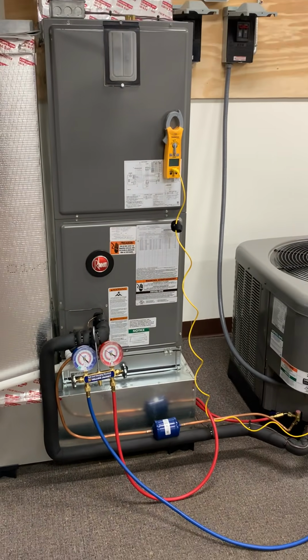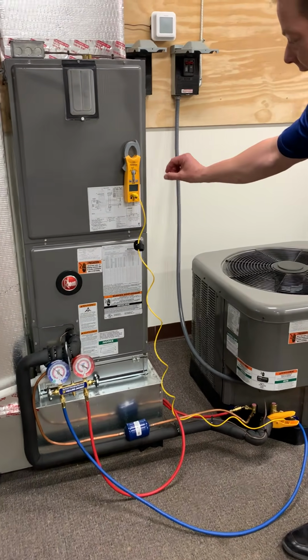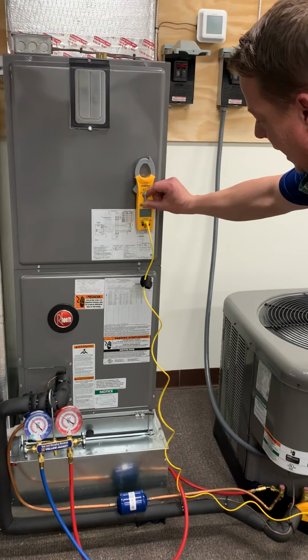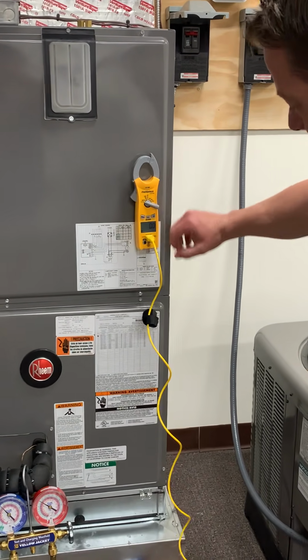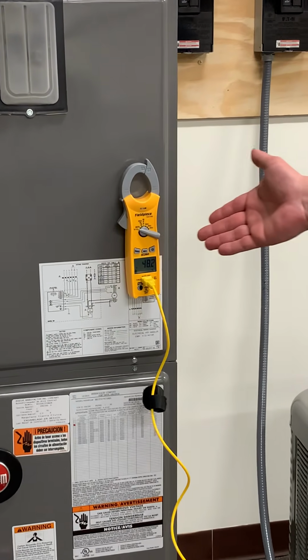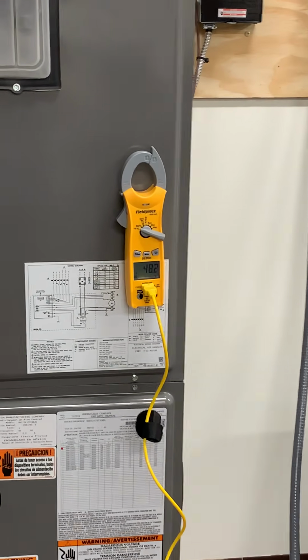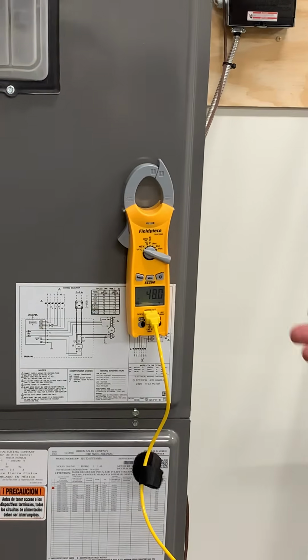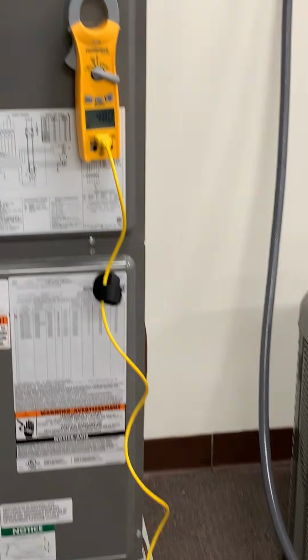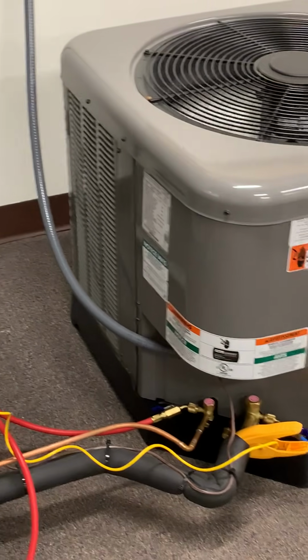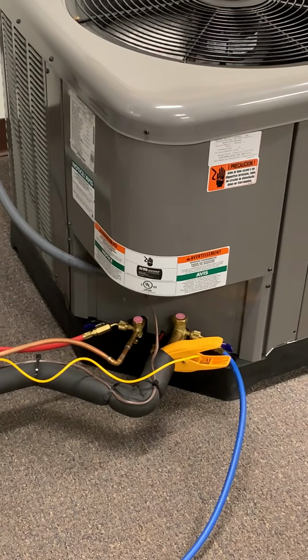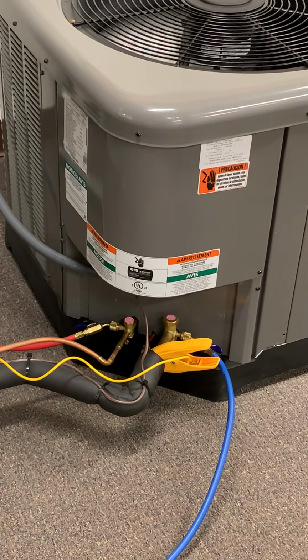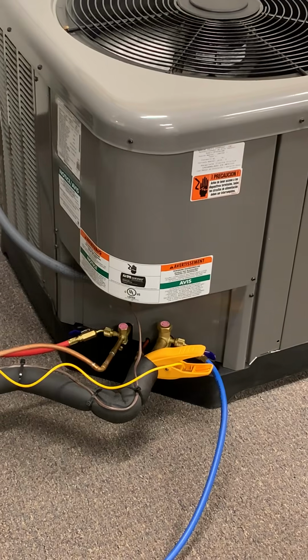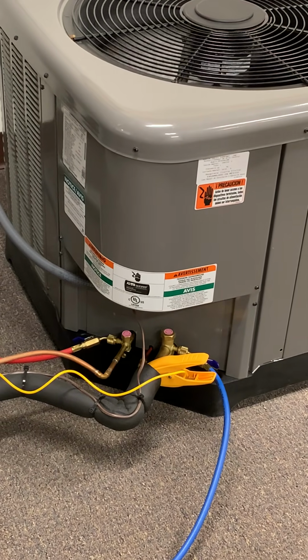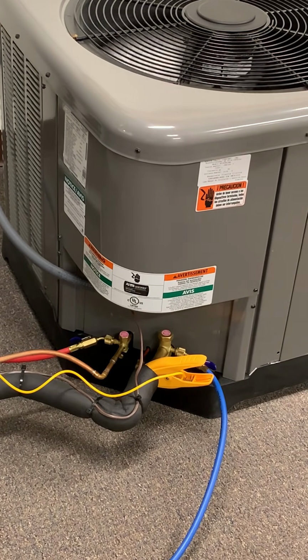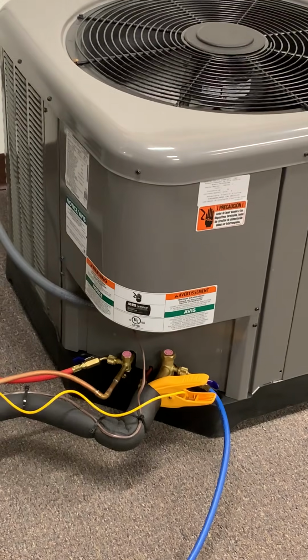So the first measurement I'm going to take is superheat, and I'm using a Fieldpiece multimeter with a thermocouple attachment, and I'm going to let this give us a second to settle out. I prefer a clamp-on type probe versus a thermocouple using electrical tape. I just tend to think we're getting more surface area and a more accurate temperature reading. So I really prefer a clamp-on type device when measuring the line temps.